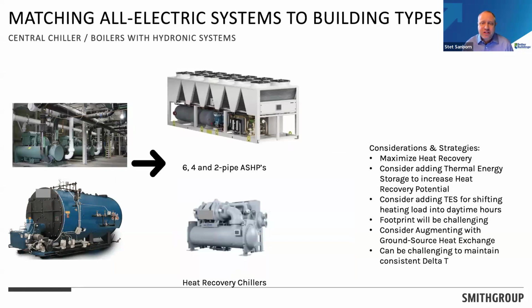So if you have classic chillers and boilers for larger scale buildings, there's a ton of systems on the market now that are 6-pipe, 4-pipe, 2-pipe air source heat pumps, as well as heat recovery chillers for your large buildings and campus scale projects. These systems tend to be modular. You can scale quite a bit with the size of your building. And they're a great resource, especially if you're looking to get rid of a heating or cooling only system and go to a heat recovery style configuration. Next.